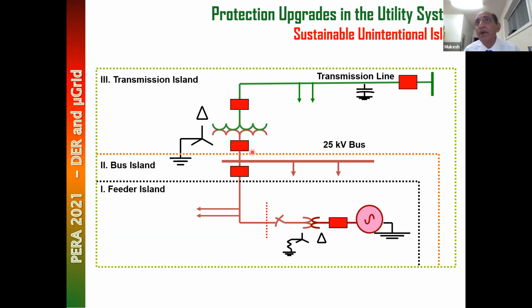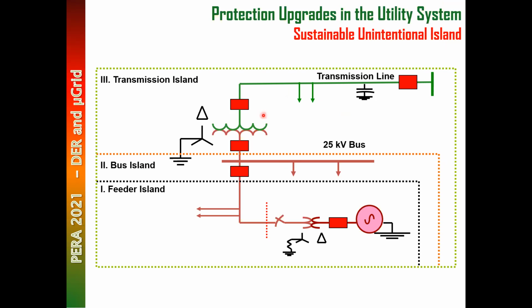Likewise, if this can form a bus island, we don't do any bus island protection upgrade on a station like a bus transmission station. What this 2:1 rule does is basically allow you to optimize your protection upgrade based on the feeder load and generation ratio, or microgrid ratio. If your feeder load is approaching the generation, then you need to do protection upgrades at the feeder level. If it's approaching the station bus level, you need to upgrade protection here. If it's approaching the transmission level, you need to add line protection. So that's how you optimize your protection.